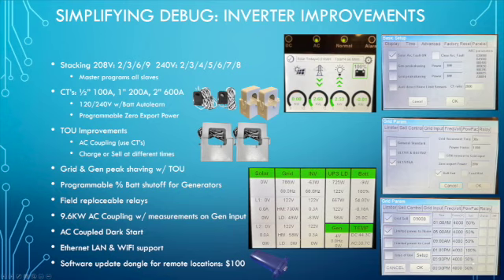We also, in the time of use column, allowed customers to turn off a generator early. Before this, the generator would charge the batteries up to almost full when it was triggered, and once it reached 95%, it would turn off the generator. Now you can enable time of use, and if you have it set to 50%, and let's say you have the generator triggered at 20%, it will charge back up until you reach that time of use battery percentage, and shut off. We also have field replaceable relays as in our earlier 12K design.